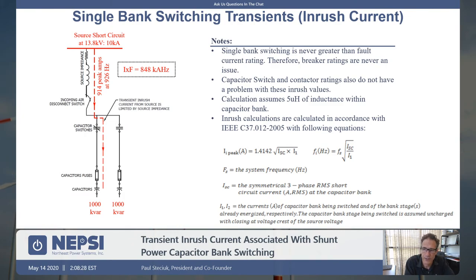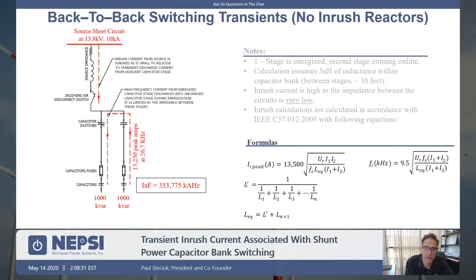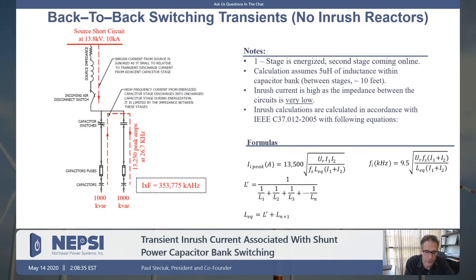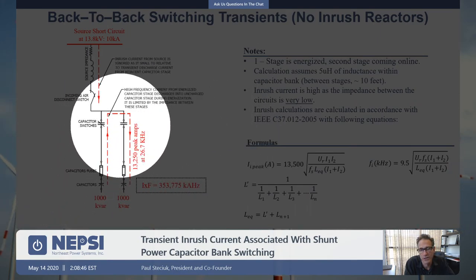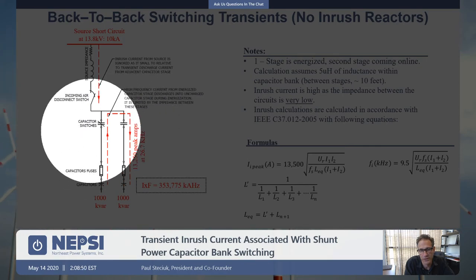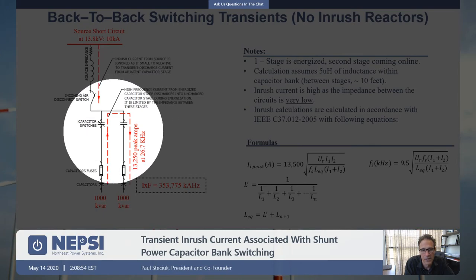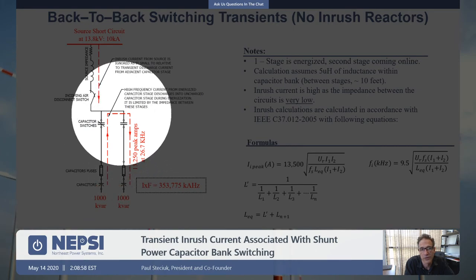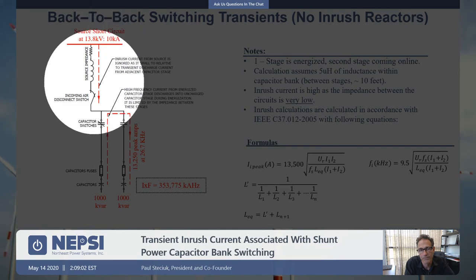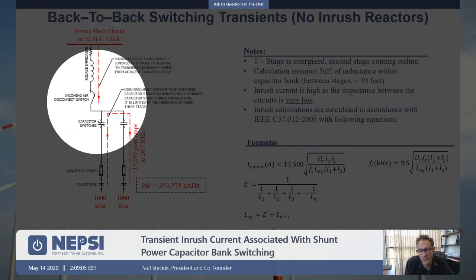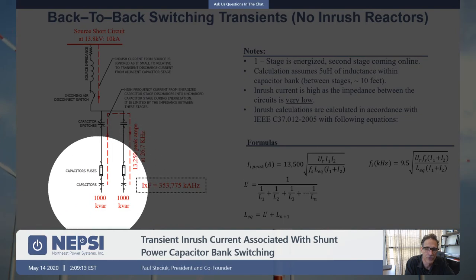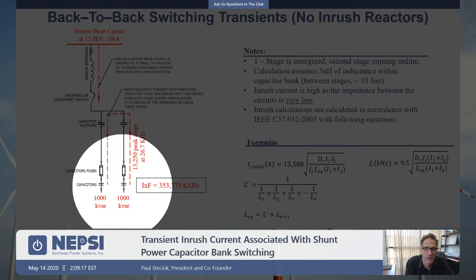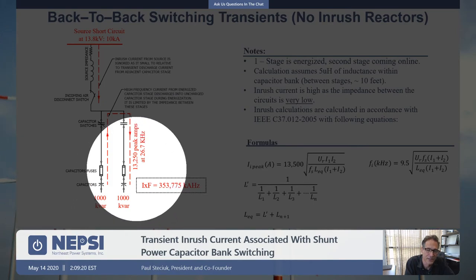We have a spreadsheet tool on our website under the resource page to do these calculations. Now, what is the inrush current if we switch on a second capacitor bank with stage one already on? When we turn on stage two, the majority of the current that flows is back-to-back switching current — a dumping of the charge on the energized capacitor into the uncharged capacitor. That amount of current flow is very significant.